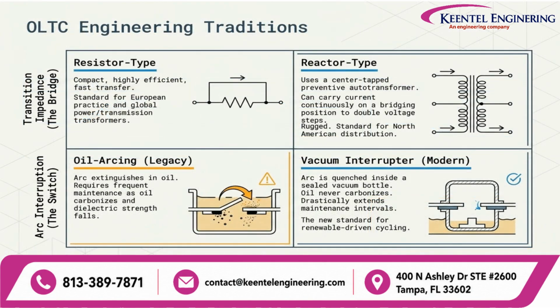Over decades of transformer development, several engineering approaches have evolved for OLTC design. Resistor-type OLTCs use transition resistors to limit circulating current during tap changes. These are compact, widely adopted, and suitable for most transmission applications. Reactor-type OLTCs replace resistors with reactors, reducing transition losses but increasing mechanical complexity. Historically, many systems used oil arcing mechanisms, where switching occurred directly inside transformer oil. While effective, these designs required extensive maintenance because of contact wear and oil contamination. Modern vacuum interrupter OLTCs have largely replaced oil arcing systems. Vacuum technology dramatically reduces arcing, minimizes maintenance, improves reliability, and extends service life, making it today's preferred engineering solution.